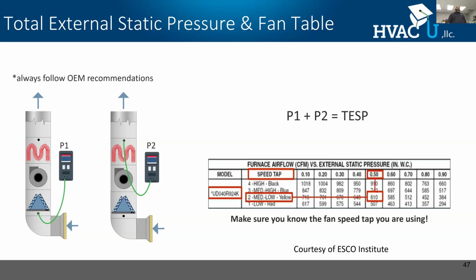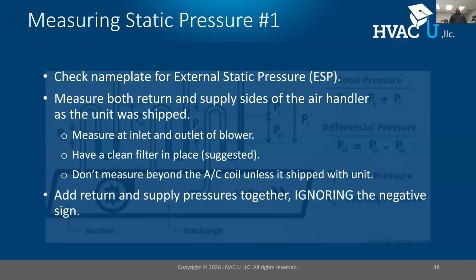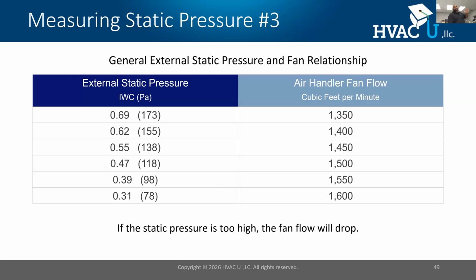When you get to static pressure, if you don't measure external, you can measure supply and return, add the two numbers together, and that will get you your total external static pressure. The way it works, you're going to fire up your equipment, get your static pressure reading, and compare it to a data plate. Here's a visual indication of what happens. If you look at the bottom of the screen here, notice how at 0.31, I got 1600 CFM. And notice how as static pressure rises, my airflow drops down. So static pressure is an awesome way, a proxy measurement, to help you understand what airflow is doing. It lets you know the higher the static, the lower my airflow through the system.